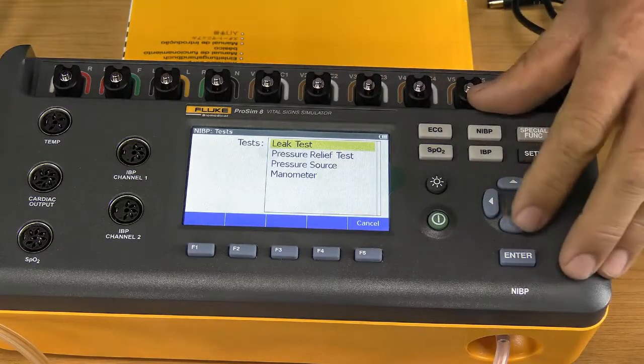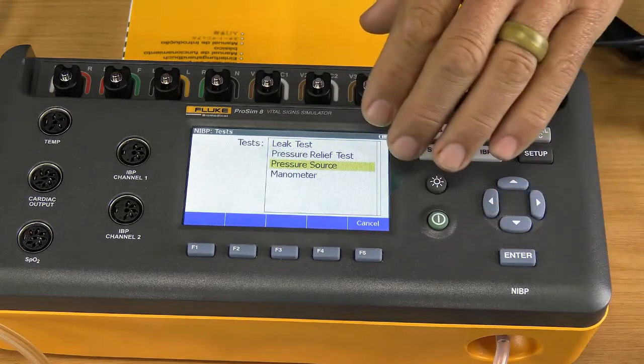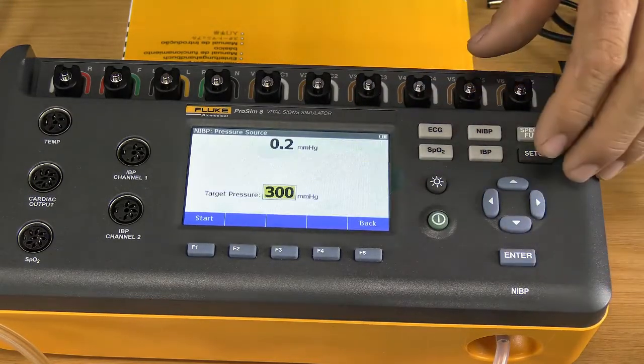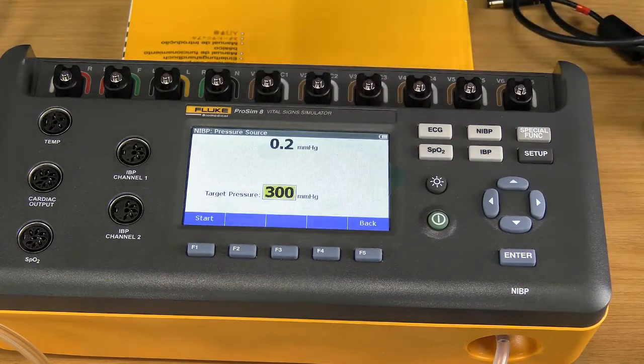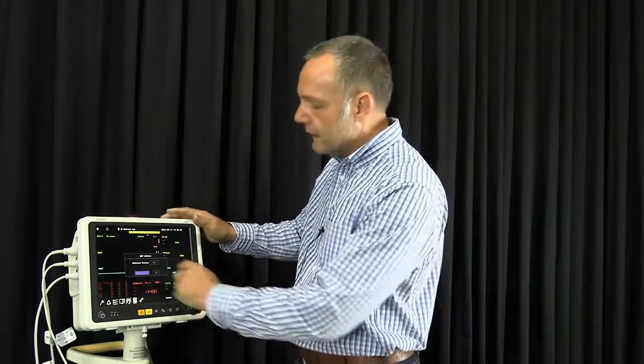Now, with a pressure relief test, that is what we test, to see if that functionality is actually working or not. Okay. The next one we have is the pressure source. If I go into the pressure source, I am using my machine to apply a static pressure. So I'm telling the pump inside of my ProSim 8, please pump up to 300 millimeters of mercury. And the pump will start, it will pump up, it will send the pressure here, and I can verify on my monitor whether the two pressures correlate with each other.